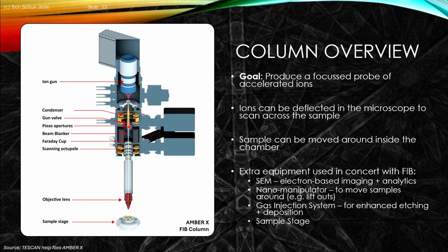Once we've got the beam in the microscope, we can then choose whether we want to blank and send the beam off somewhere else, or we can put it on our sample when we need. And then this beam, when it's behaving itself and we like it, can be sent down the microscope, and we can go through effectively a scanning octopole that enables us to deflect the beam across the surface of our sample. And then we have basically the objective lens and the end of the pole piece, and then it inserts itself into the electron microscope to enable us to target this at our samples themselves.